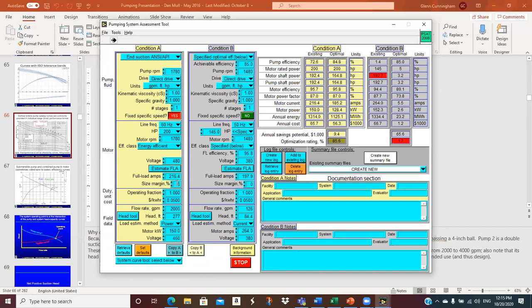Size margin, many motors are sized with a service factor. I don't know if we've talked about service factor in here. You look on a motor and you see it stamped on the tag. It'll say SF or service factor. A lot of times you'll see a number like 1.15. What that means is that motor can be run at a 15% overload successfully, supposedly. It's probably not a great idea, but it's supposed to be able to do that. So if you had a 100-horse motor with a 1.15 service factor, it would be capable of outputting 115 horsepower. So that's what service factor is. In this case, I could put a service margin in here of 15%. I wouldn't put 115, I would just put the 15 in here.